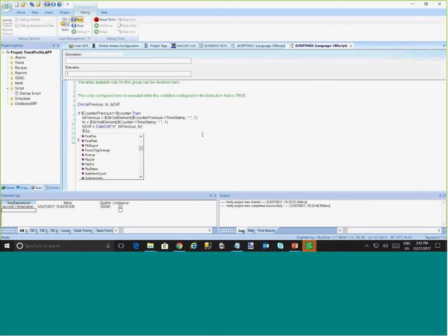So gallon per minute, for example, if you have this tag, is going to be a constant divided by this time, and that's it. So you always have the instant gallon per minute every time you get a new counter. And the longer it took you to get the counter, the lower your gallon per minute is going to be.